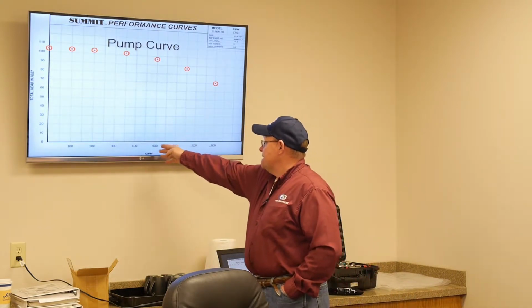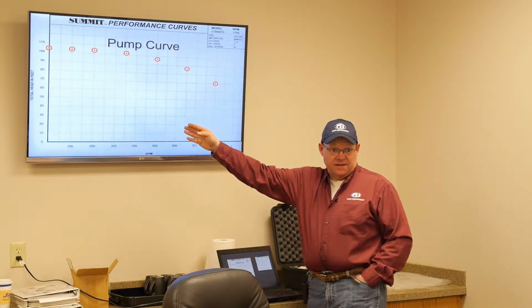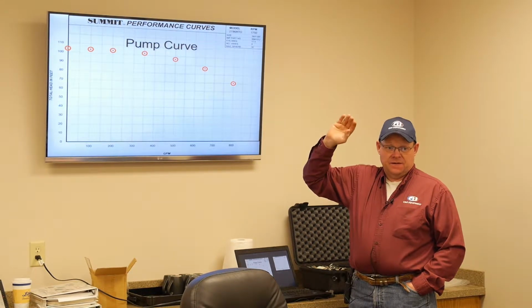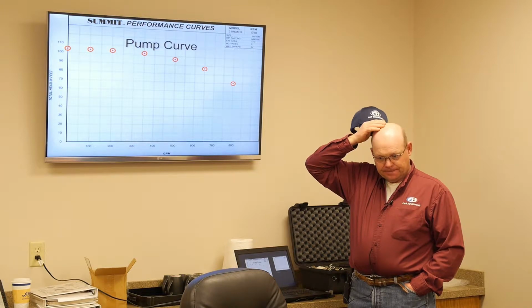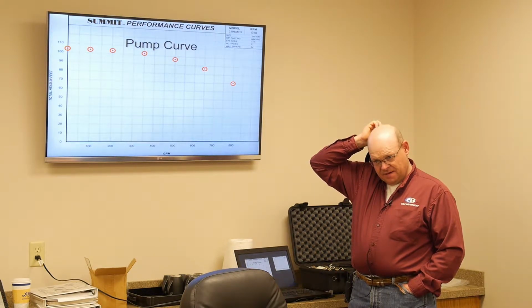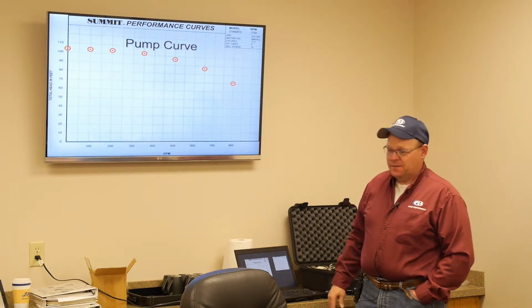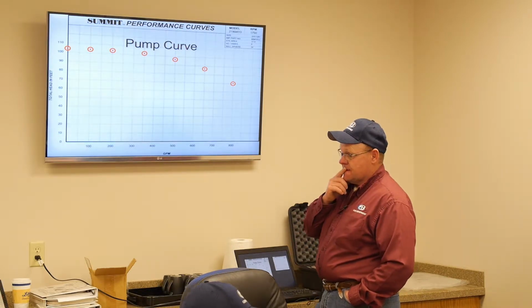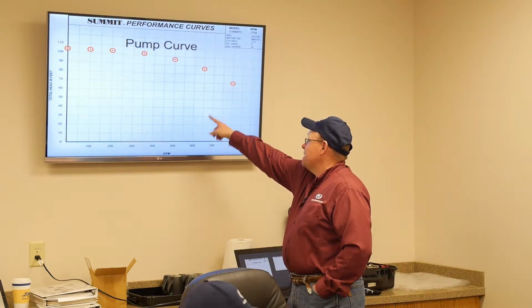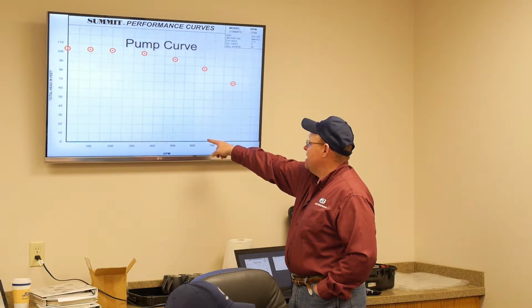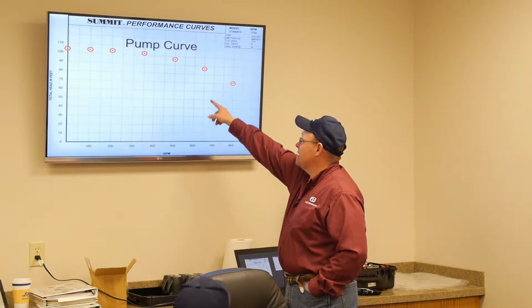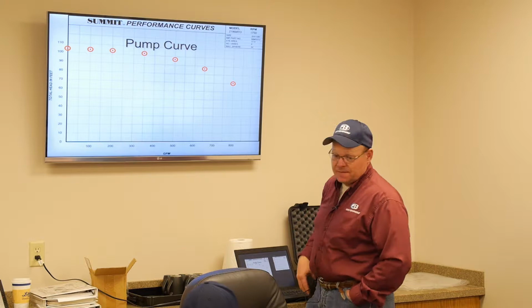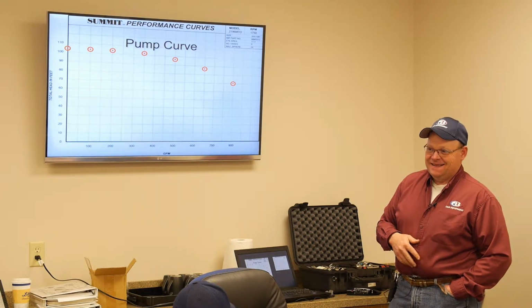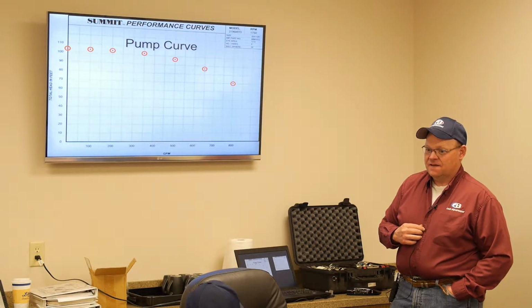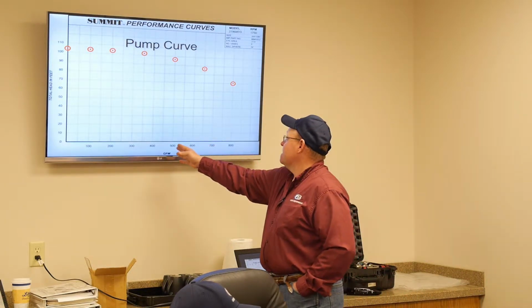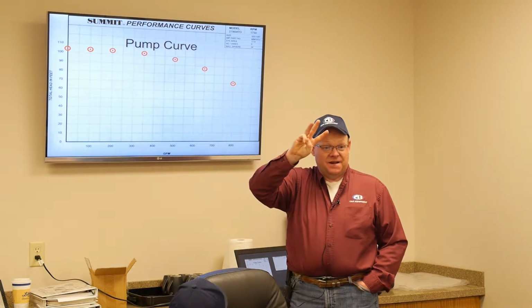So for this example right here, we have 500 gallons a minute at nearly 95 feet of head. Does that make sense? Okay, so somebody take 95 divided by 2.31. Okay, write that pressure down somewhere. 41.25. Okay. Now over here on the same curve, this pump will do 650 gallons a minute at 83 feet of head, or what is it, 87? Somebody? 88. So 88 divided by 2.31 is 38.09 or 38.10.